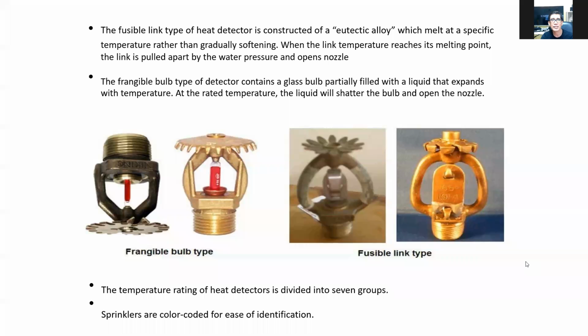Okay, so we have the fusible link type of heat detector, constructed with eutectic alloy, which melts at a specific temperature. We have the frangible bulb type of detector, which contains a glass bulb partially filled with liquid that expands with temperature, with a rated temperature. So this is the frangible bulb type. This is the fusible link. This fusible link has a material that will melt and it will activate the water. This one has a bulb which contains a liquid, and if it expands, it will trigger the nozzle to release water. So this liquid will shatter the bulb, and automatically the water will go out.